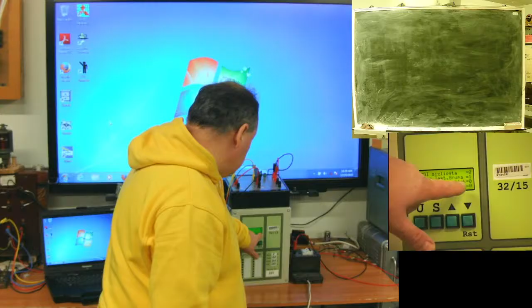When the configuration of the network changes, I don't know, a line connected or disconnected, you don't need to... okay, let's be less correct. Your personnel in place, maybe, how to say, low competence personnel. Allowing them to change all settings is stupid. It's risky. What you're doing, if you understand what your substation can operate with, one line or two lines, with one transformer or two transformers, you create a set of settings, and the device receives a binary signal for the activation, which settings group to use.